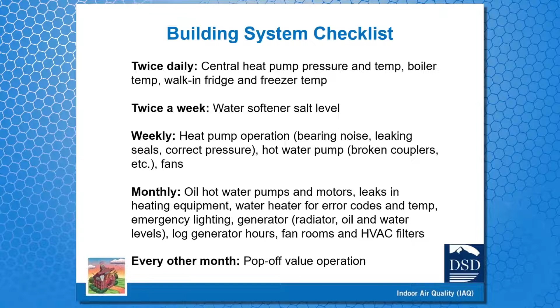This gives you an example of some of the things we do at one school on this building systems checklist. I'm not going to read it all, but just to give you an example: twice daily we check the central heat pump pressure and temperature, the boiler temperature, and the walk-in fridge and freezer temperature. Weekly, we check the heat pump operation, looking for bearing noises, leaks, and making sure the pressure is correct. We check the hot water pumps, looking for broken couplers or anything concerning, and we also check the building fans.